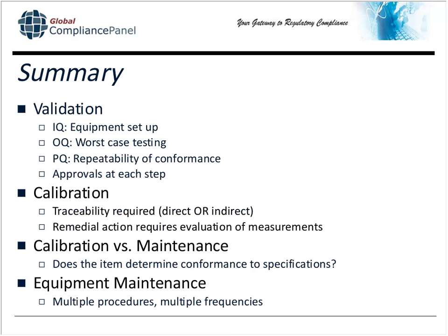So, pulling everything together, and I know it was a lot, I hope that you got a lot out of this. On IQ validation, the IQ is the equipment setup. Is the equipment set up acceptably? In the OQ, we're going to determine the worst case testing. We're going to take steps to show what parameters result in bad subassemblies or devices. The PQ assures repeatability of conformance at the nominal settings, and you've got to have approvals at each step. Calibration requires traceability, whether it's direct, in which case you send things out, or indirect, in which you use standards that are sent out directly.